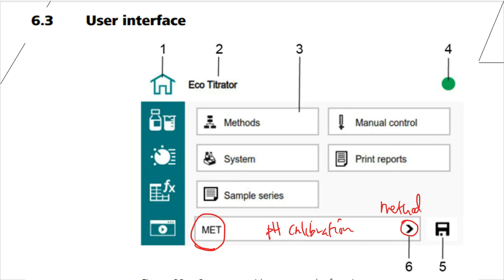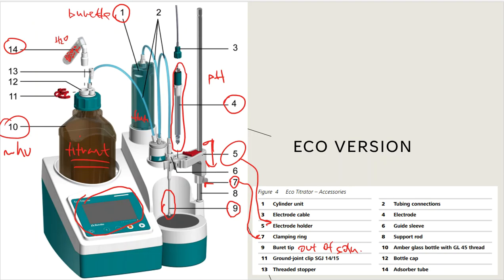So when you pick pH calibration, it's going to prompt. It will show up here in the line item after you select it, and then you will hit the play button that's down at the very bottom of the touchscreen panel. So if I go back and take a look at the Eco Titrator, right here is our play button. Ta-da! Right there. So you're going to hit it, and then it's going to say, put on your buffer. And then you put your buffer on, and you hit enter or play again, and it will measure that buffer, and it will give you the millivolts.